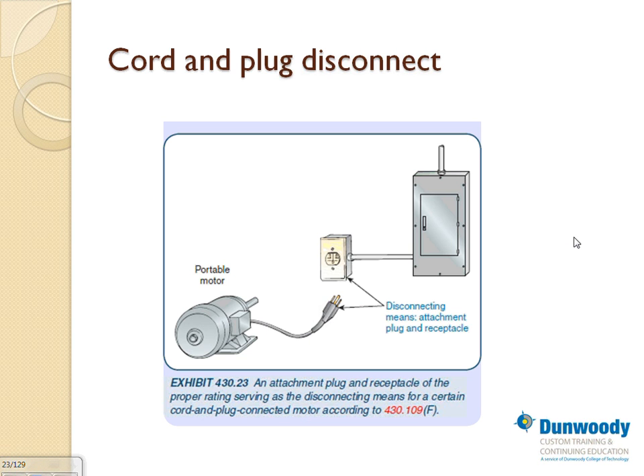Any comments, guys, about the disconnects? So the typical rule is the disconnect next to the equipment. The exception is to have the disconnect somewhere else. Either way, especially if it's out of sight, you have to be able to lock it and tag it. If not because of the code, because of OSHA. You can't work on equipment if you can't lock it, tag it. Because we're tired of people leaving their hands behind when they're fixing equipment, right? Machines start, chop somebody's finger.